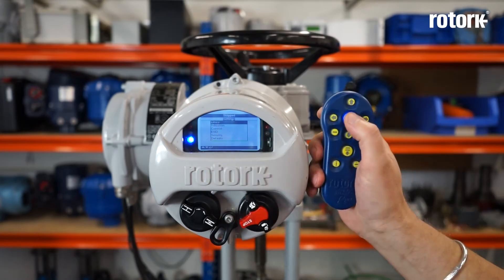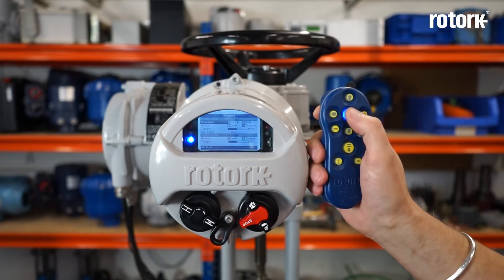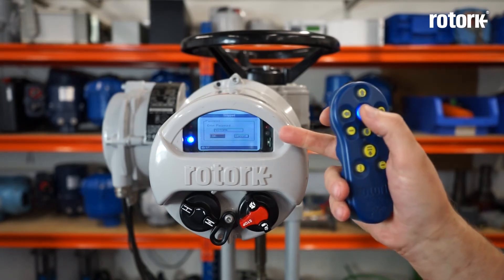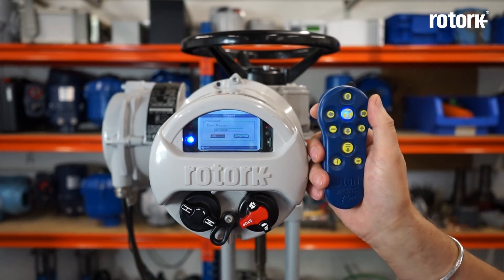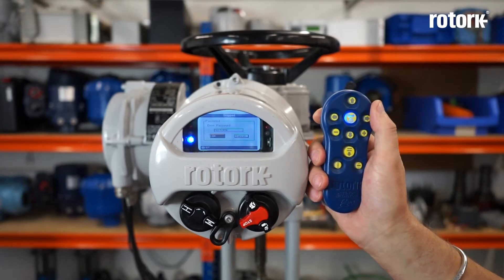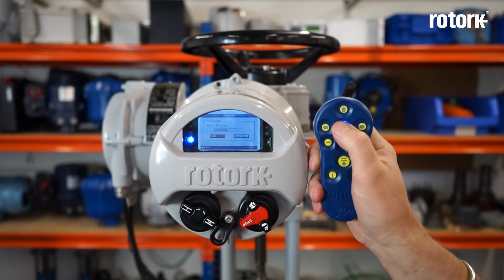It's very easy to set the limits and adjust the torque values of the actuator, and the basic setting only takes a few minutes. Press enter when you reach the limits — this is the main limit page. From here I press enter and I am taken to the enter password screen. The settings display is password protected and you must enter the password to change any parameters. The default password is ROTORK, so there is nothing to remember — all you have to do is press enter.